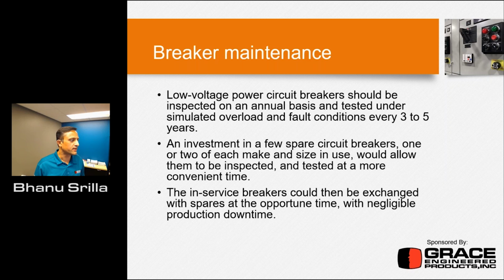The next one is the investment in a few spare breakers. As I mentioned before, you can have similar identical pieces of equipment in store, like 2 or 3. That will help you, if something goes wrong, to bring in a spare and put it back in service. The in-service breakers could then be exchanged with spares at an opportune time. These are things where you can cut down the downtime significantly, and the more you cut down the downtime, the more it helps you keep your operational output and productivity measures at a high rate.